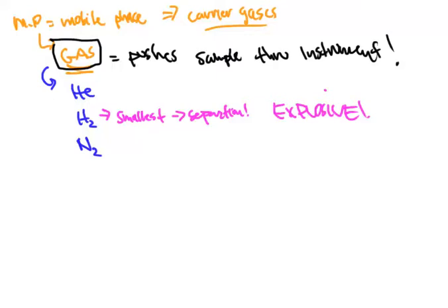Now, we don't really keep hydrogen tanks in the laboratory. We generate hydrogen as we need it. And we have something called a hydrogen generator that does that for us. And this basically uses water. And water's H2O. It takes water and breaks it up and releases the hydrogen content from water and feeds it to the GC on the spot. So that way we're not lugging around explosive hydrogen tanks and sitting them in the corner of the laboratory to blow up at any point in time.